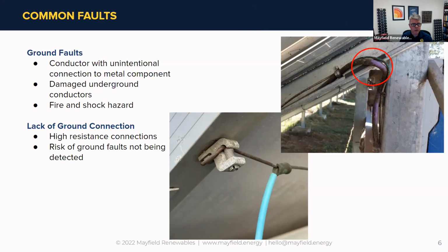Another issue we'll discuss, relevant to the IEC standard, is a lack of a ground connection. The picture on the bottom left shows how equipment grounding connections were done before UL 2703 racking systems existed. They'd use a lay-in ground lug, drill a hole in the frame since the marked ground point was behind the racking system and inaccessible, use a nut and washer to connect the lug to the back of the frame, then run a bare copper wire from module to module to create that bond. There are hundreds, if not thousands, of systems out there built this way.